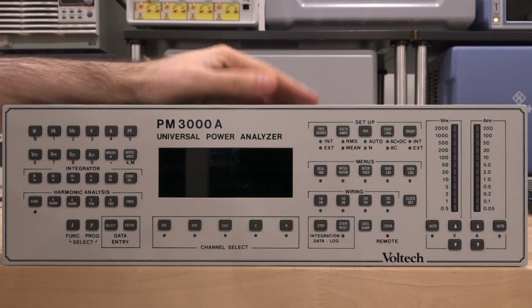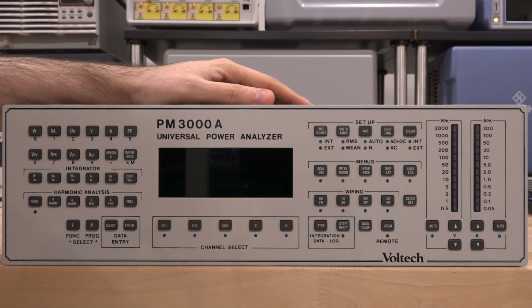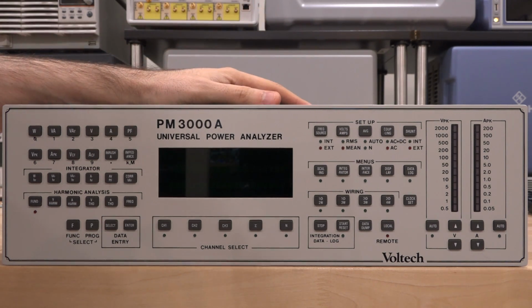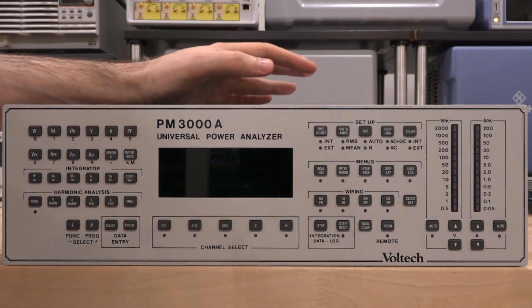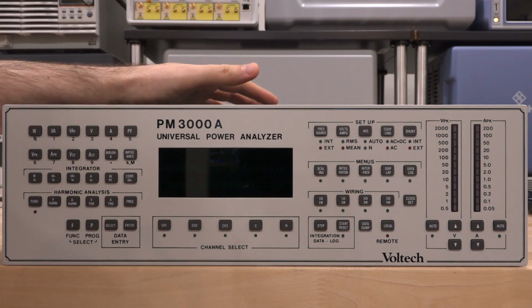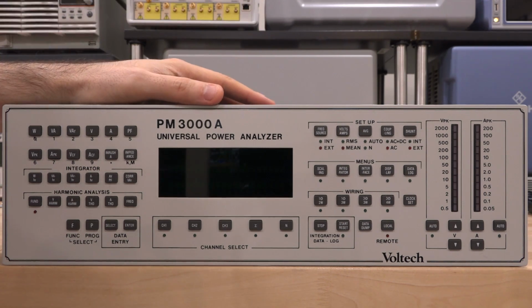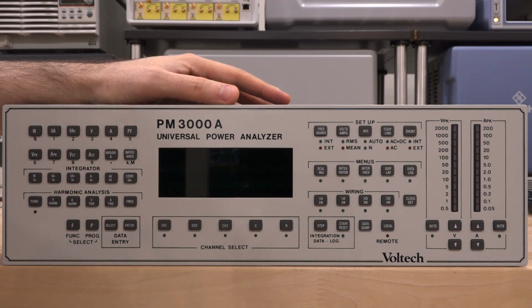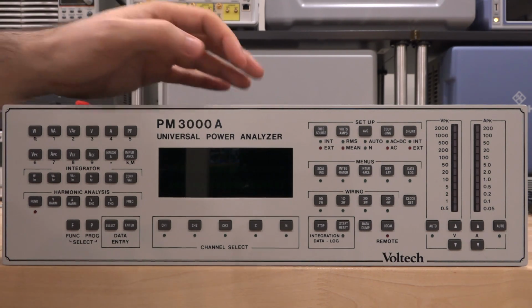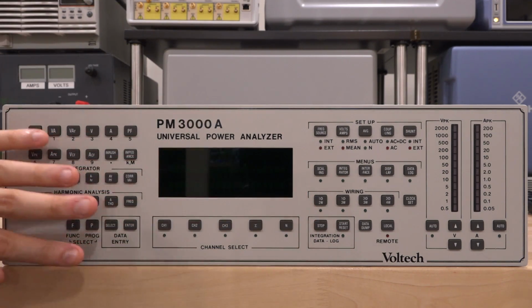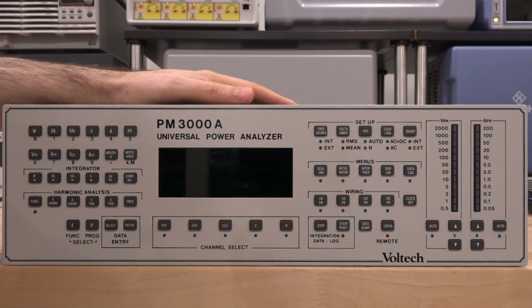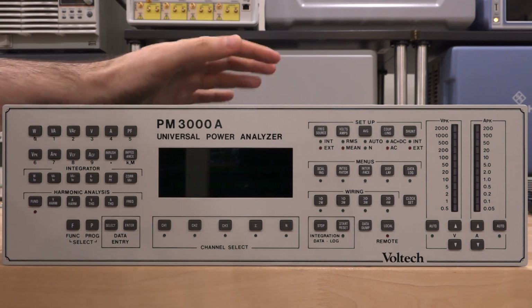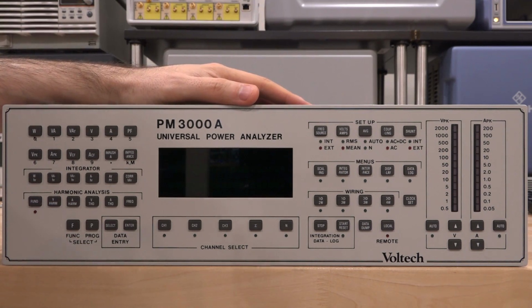The challenge of these instruments is creating these channels to have a huge dynamic range and common mode rejection from each other, because you can have thousands of volts of different voltage between the 3 channels, and they have to be very well isolated from each other. Aside from them being isolated from each other, they also have to be completely isolated from all the digital circuitry that's in here, because after you do the analog to digital conversion, you cannot couple those directly to all the DSP that's built into here, and certainly not to the user interface, because you cannot have those voltages couple in. It can be lethal if something goes wrong. So this is going to be an exercise on really nice isolation techniques once we take a look inside and see how it is built.